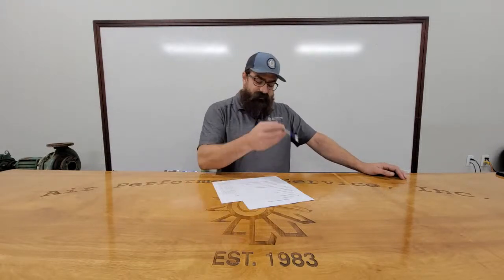The next thing, what Jason mentioned, was a multi-zone. So there's two kinds of multi-zones that we have in Texas. They're typically face bypass. They actually nicknamed them Texas multi-zones for that reason, because we don't use the heating side of them. But you can have a hot deck, cold deck multi-zone, which has a valve for heating and a valve for cooling.